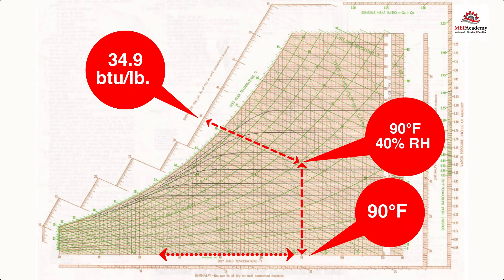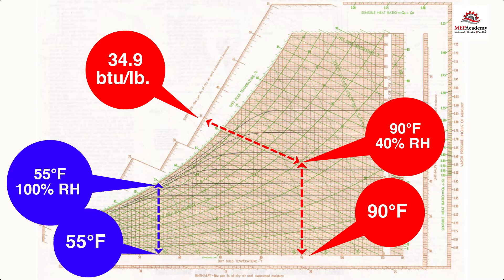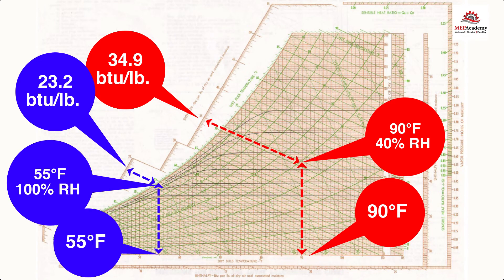Then we plot the leaving air conditions of 55 degrees Fahrenheit and 100% relative humidity. We get an enthalpy of 23.2. 34.9 minus 23.2 gives us an enthalpy of 11.7 BTUs per pound.